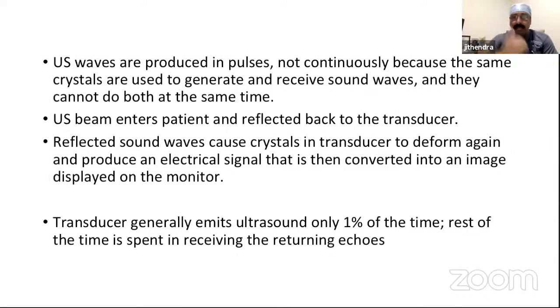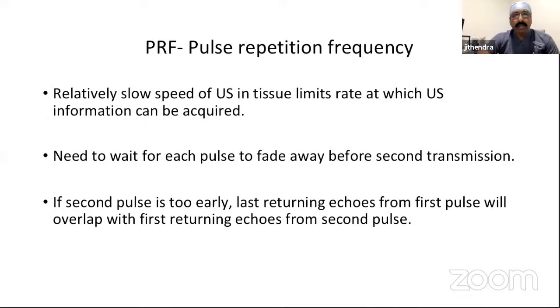The sound waves have to come back to the transducer, and the piezoelectric crystals have to be stimulated, and then impulses are sent. The electrical signals are sent to the monitor. So the ultrasound beam enters the patient and is reflected back to the transducer, and the reflected sound waves cause crystals in the transducer to deform again, producing an electrical signal that is converted to an image and displayed on the monitor. Normally the transducer emits ultrasound for only 1% of the total time. The rest of the time is spent receiving the echoes. Now there's something on the machine: when you switch on the machine, you'll find the pulse repetition frequency.